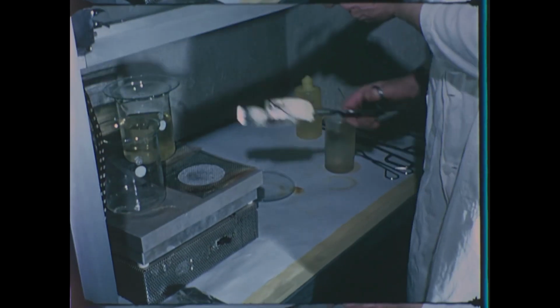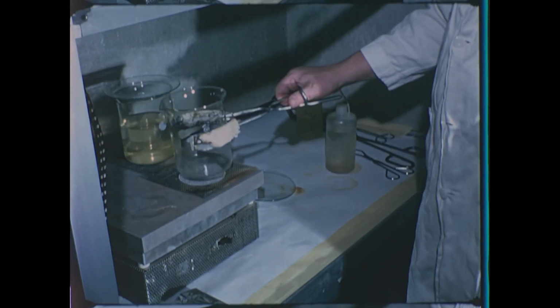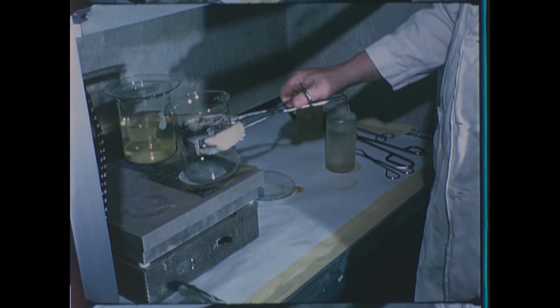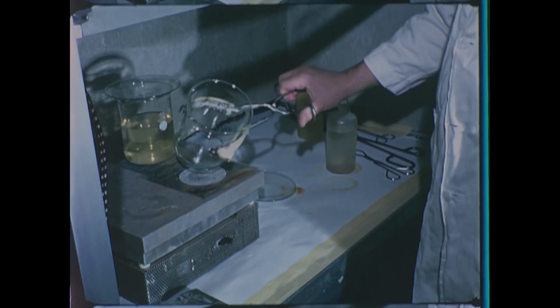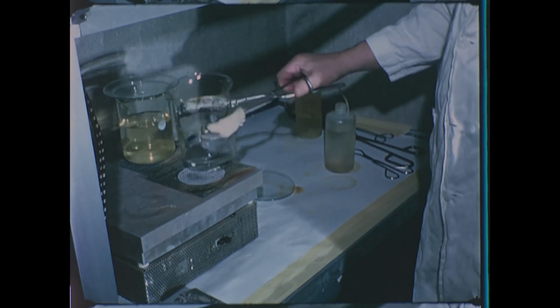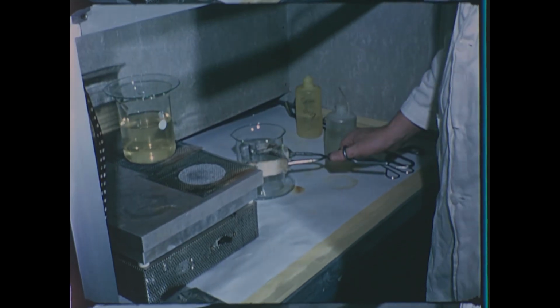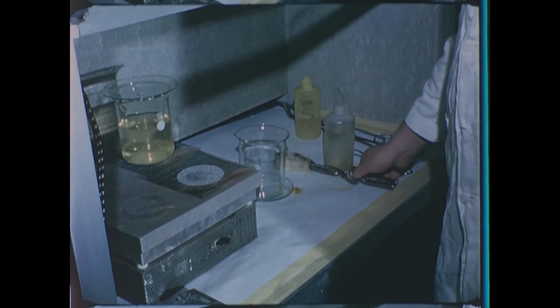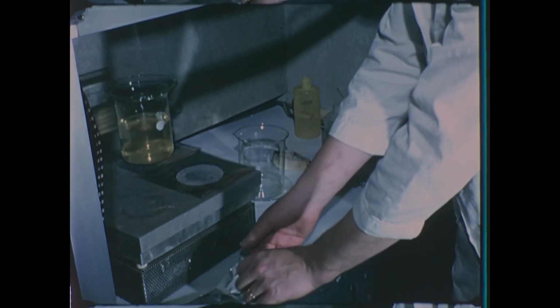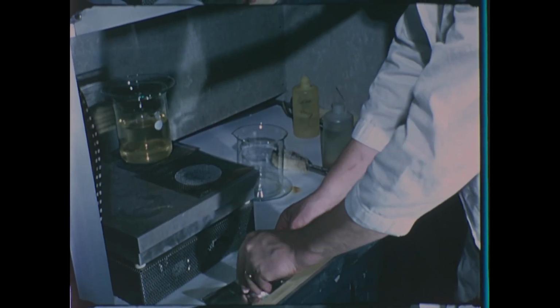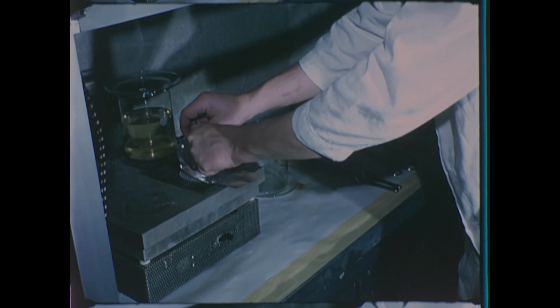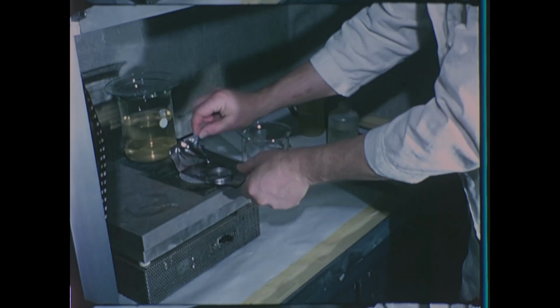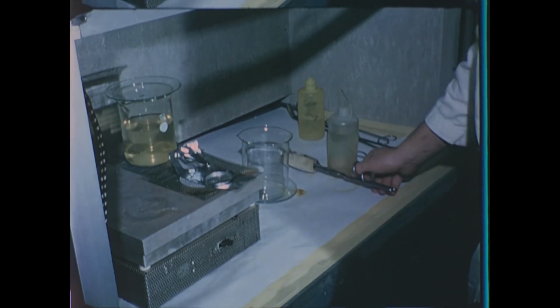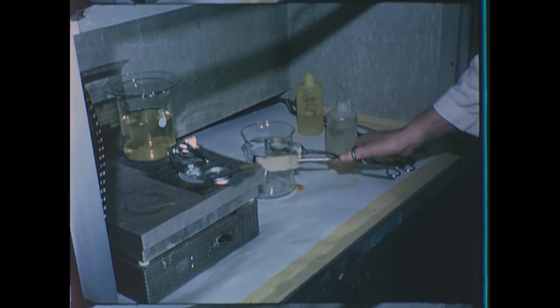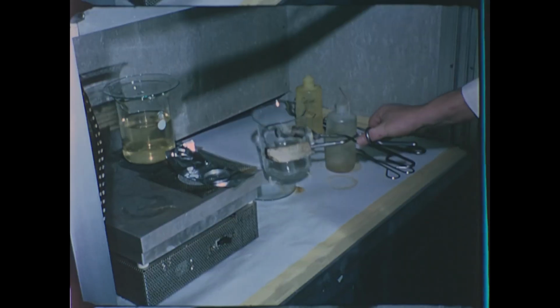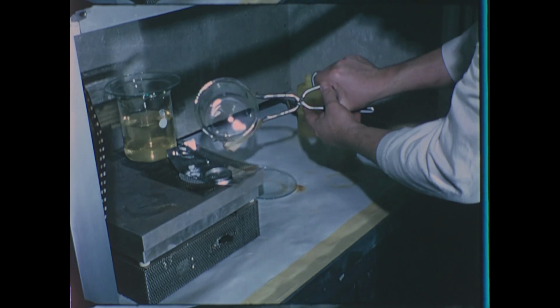Water taken from the radioactive waste disposal system evaporator overhead is sampled for radioactivity analysis. If radioactivity and chemical purity are within acceptable limits, the water may be reused by transferring to the condensate storage tank or directly to the shield water system. Unsuitable water, if within limits for discharge to the environment, may be discharged overboard. If not within limits, it must be reprocessed before discharge.